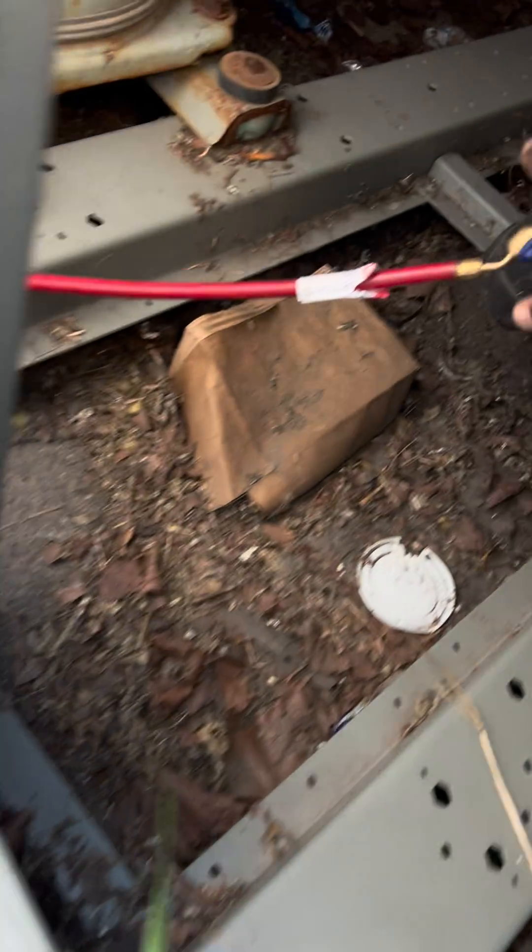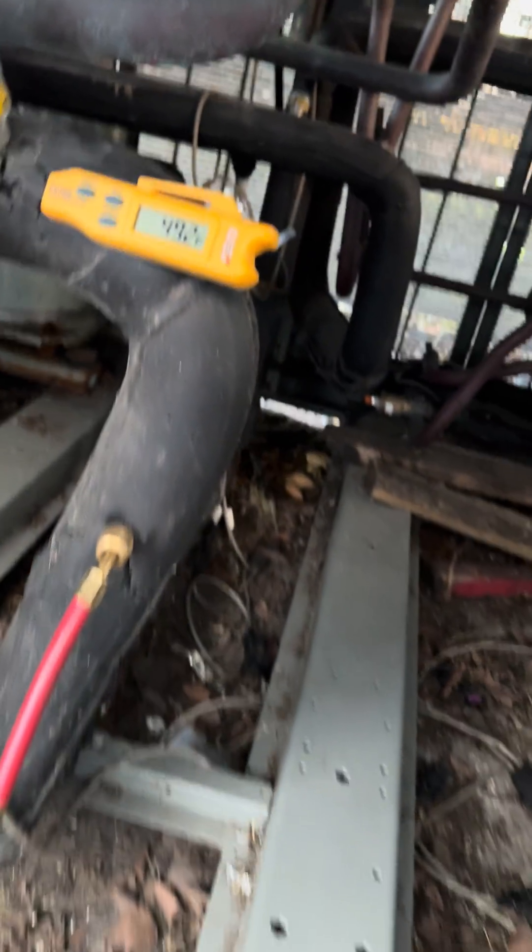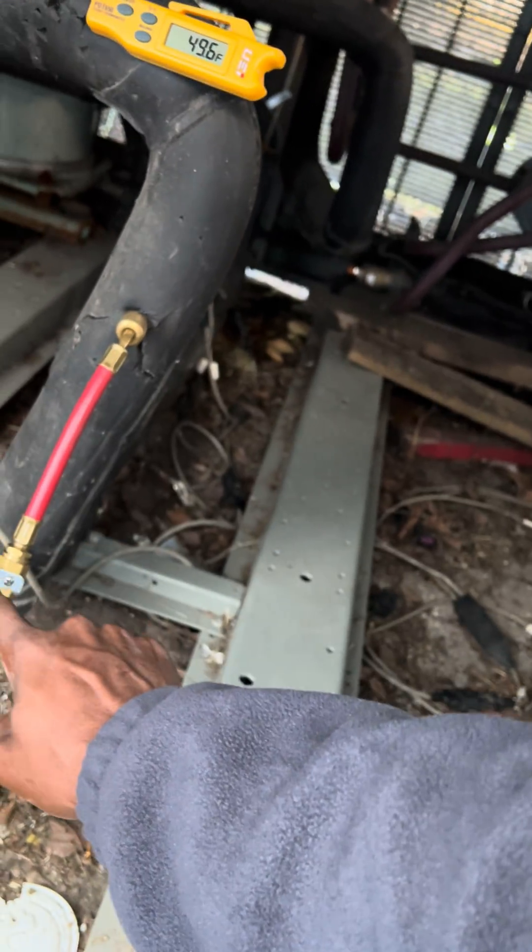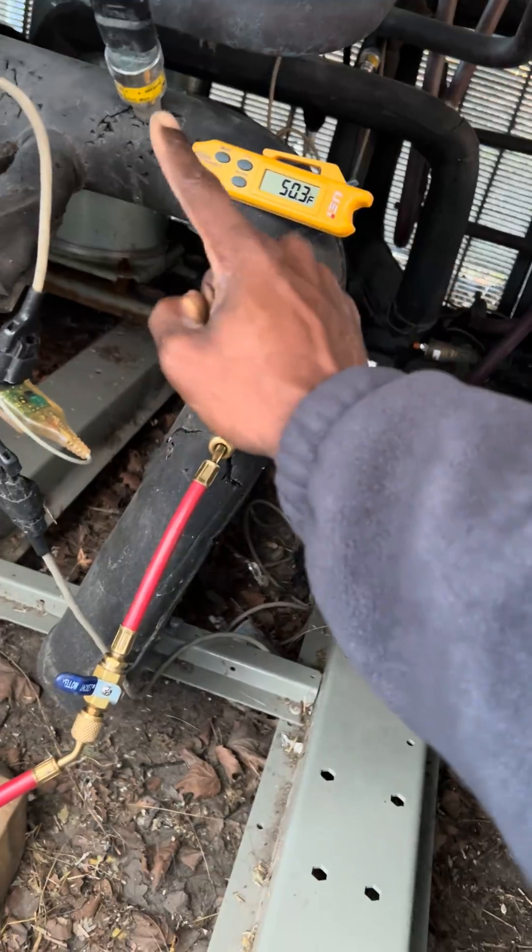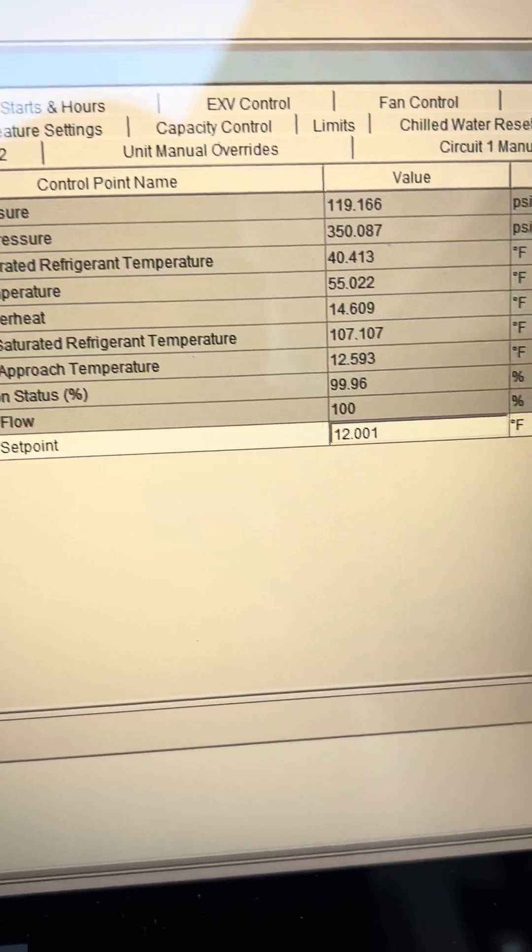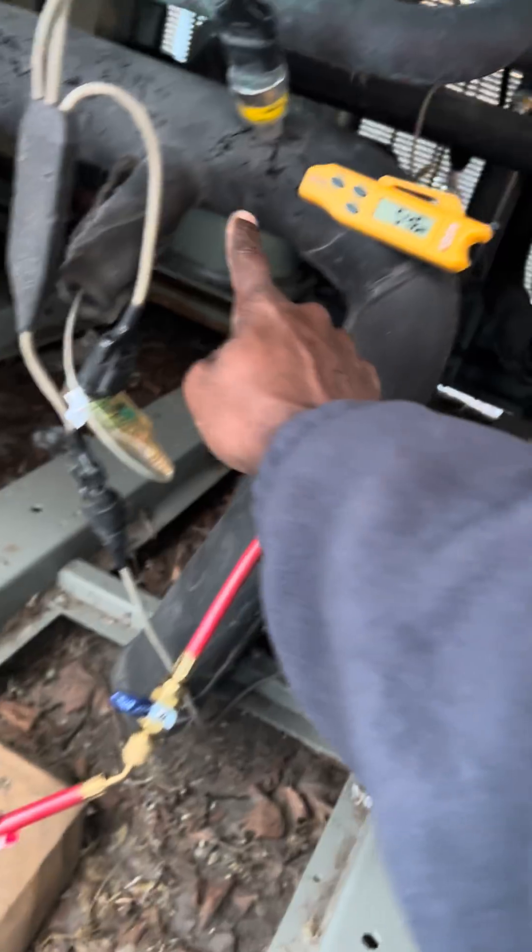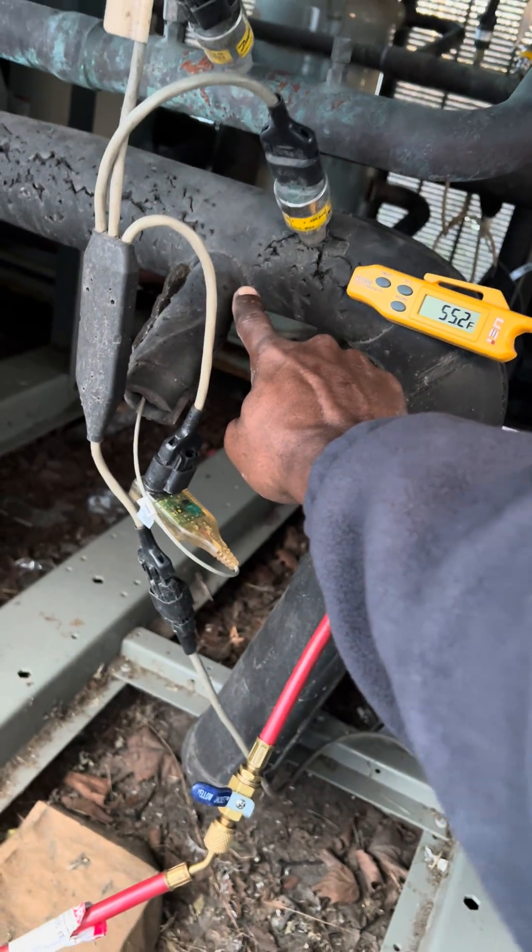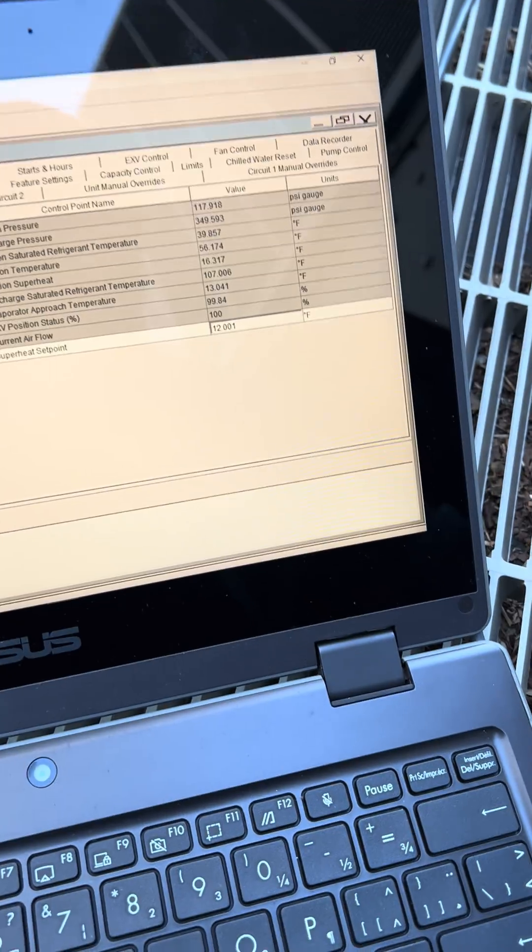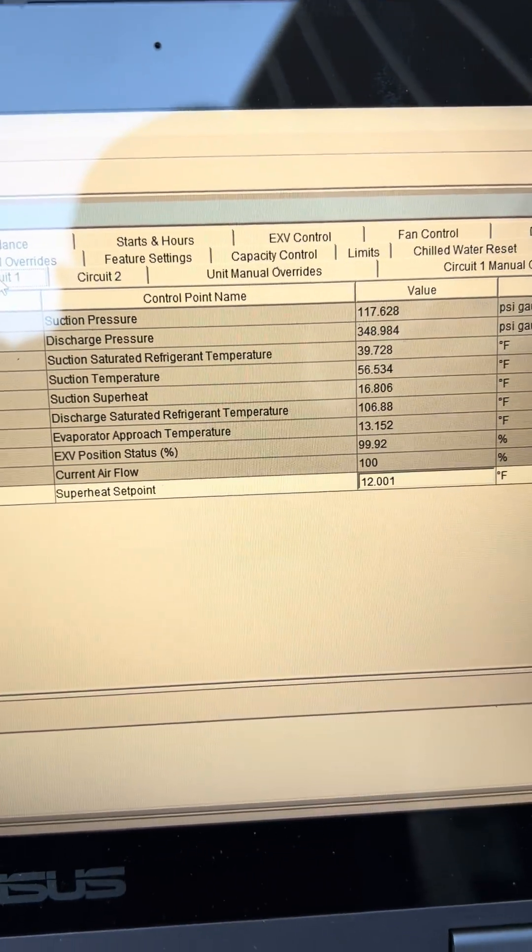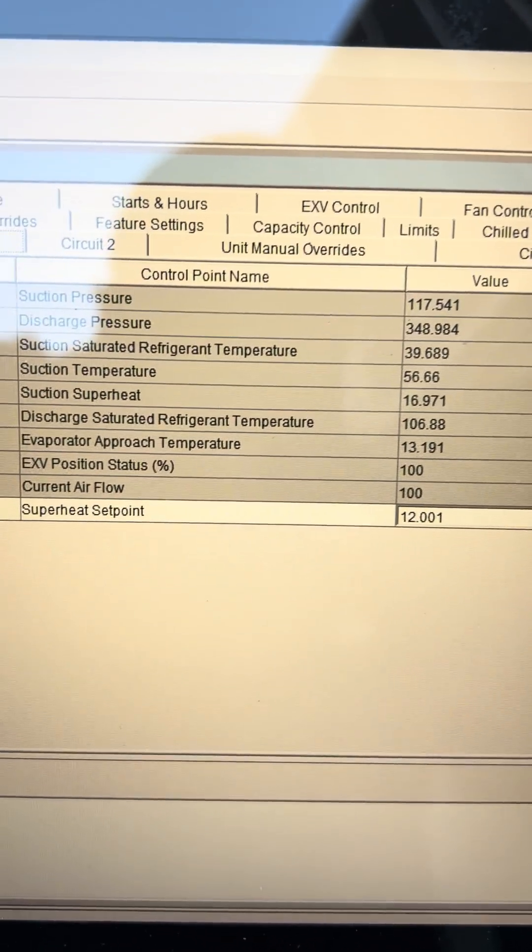Okay that's dropping because obviously the gas is passing through a liquid. Let's see what the actual numbers look like. Superheat is down but that sensor is right there as well, suction line temperature sensor. So let it circulate for a little bit and stabilize and let me see what we're going to get.